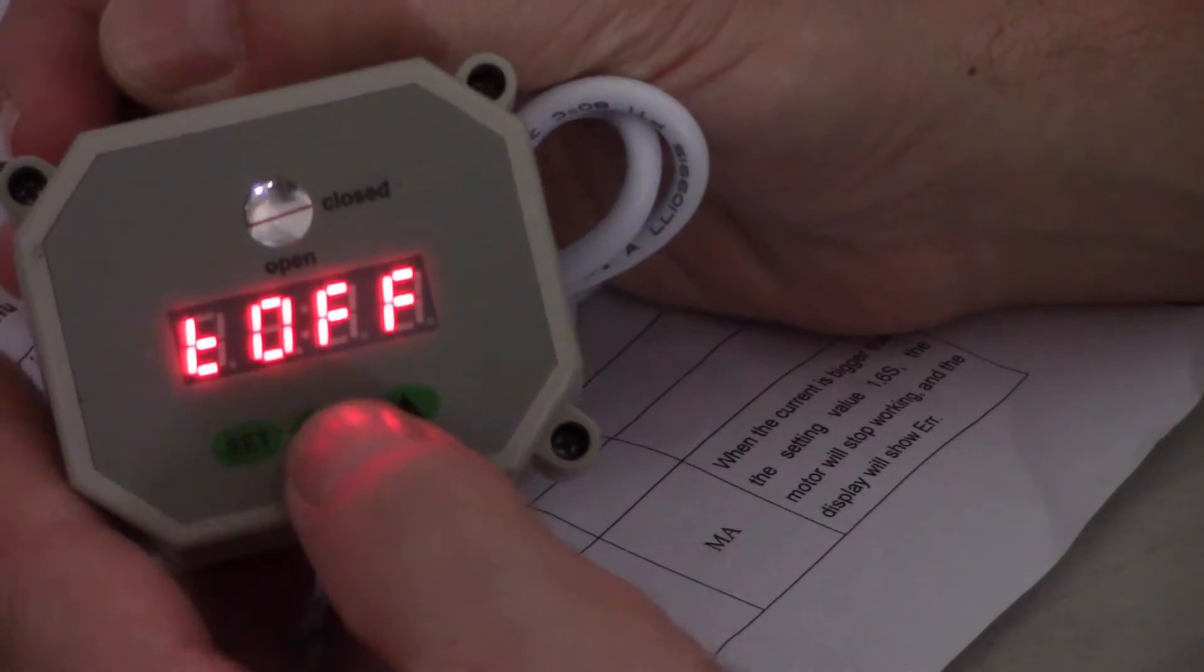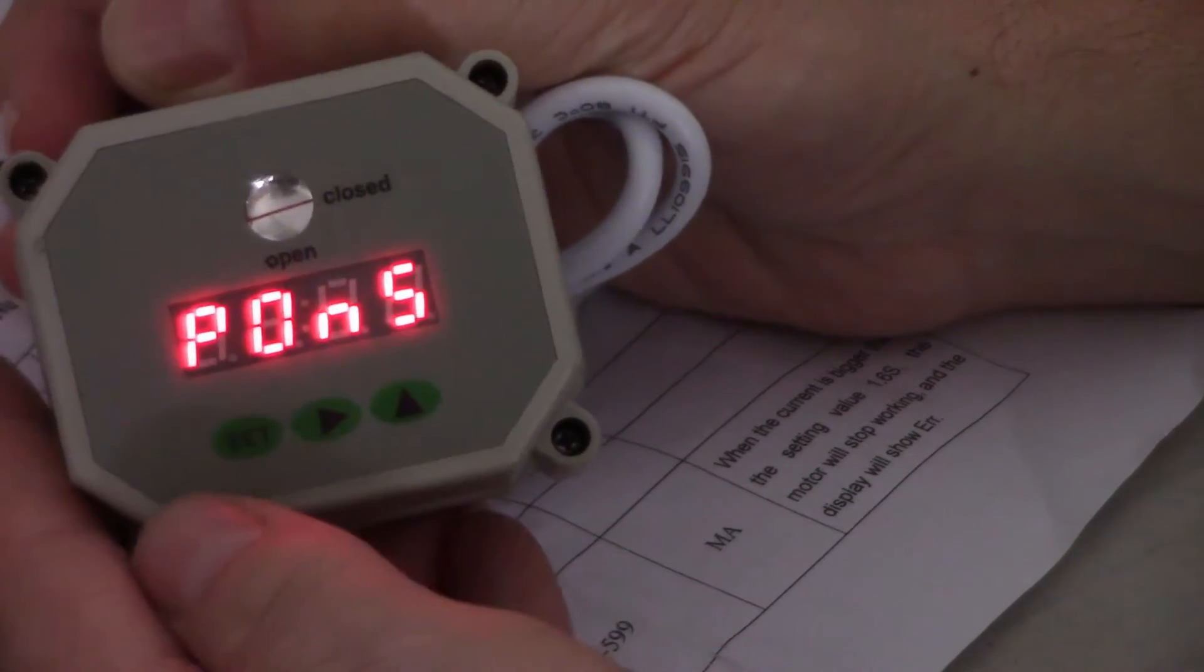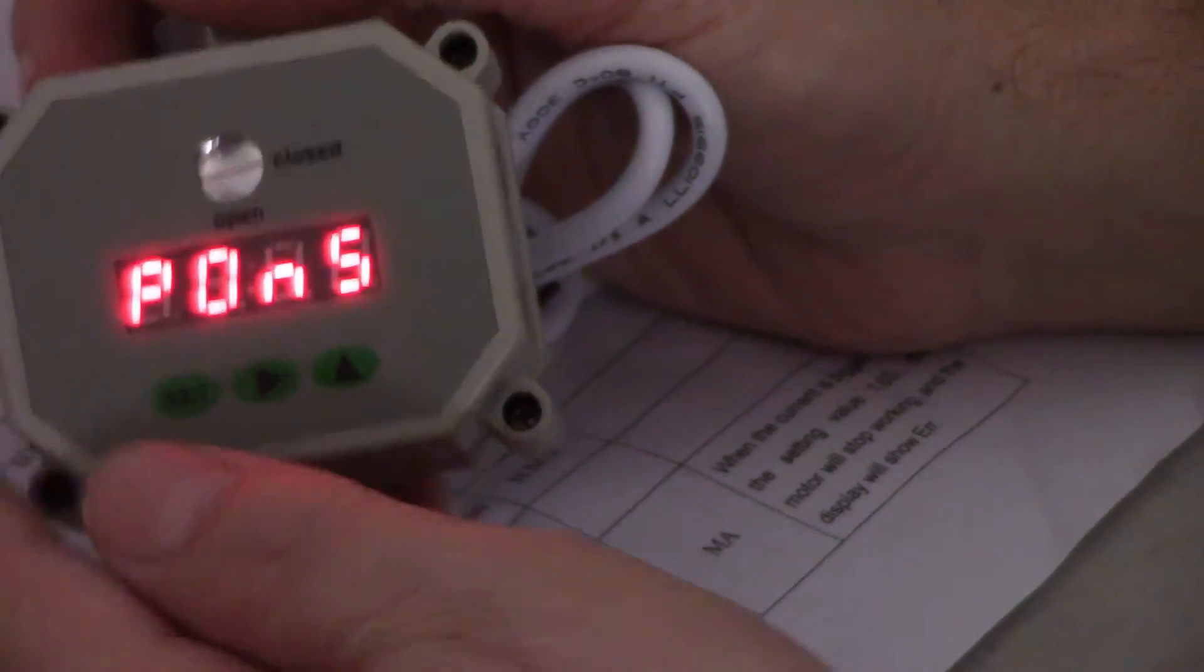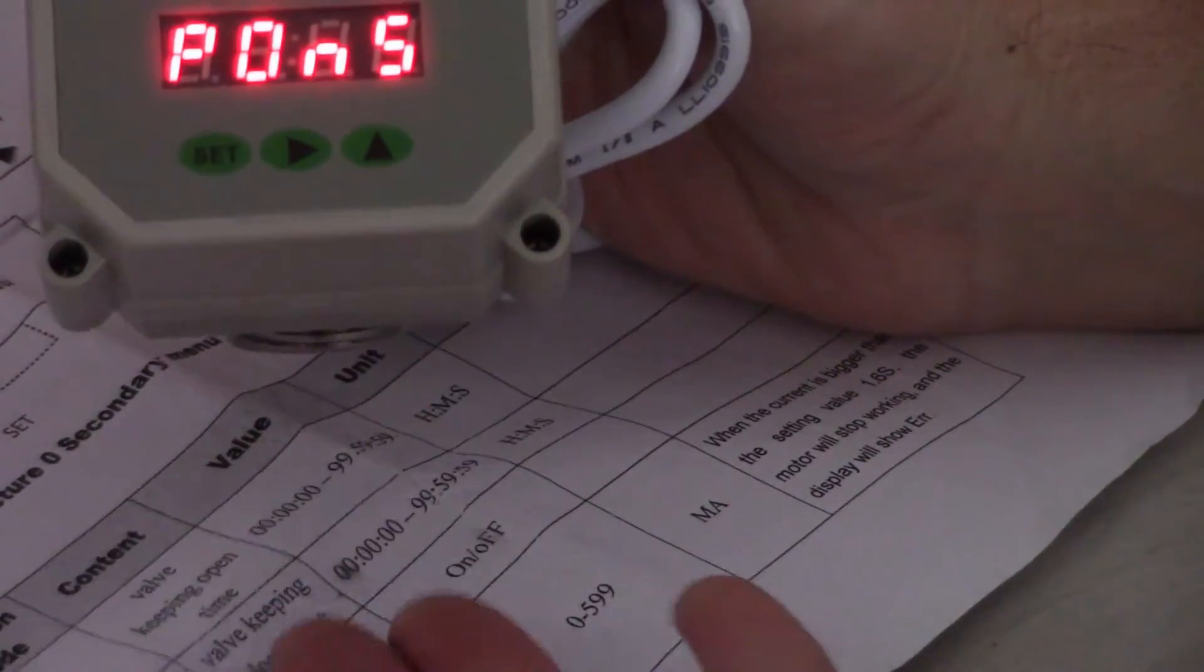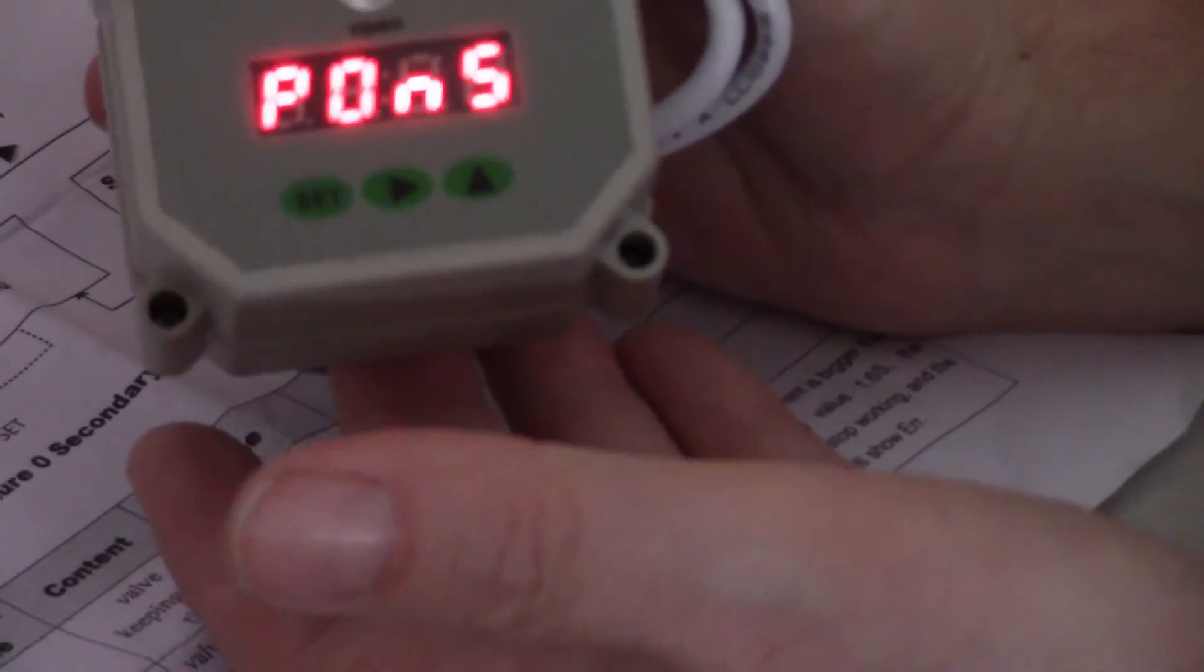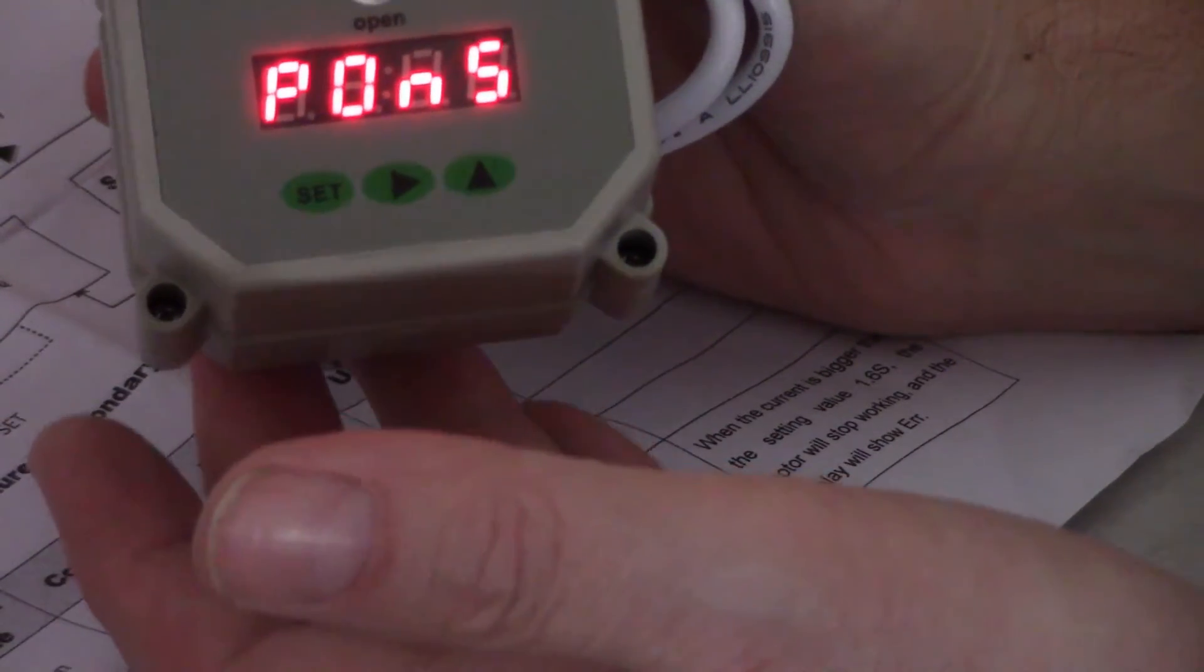Press the set button again. This is if something were to become jammed, if something were to get through into the ball valve that opens and closes, it would cause the motor to want to run and it would start drawing amps.